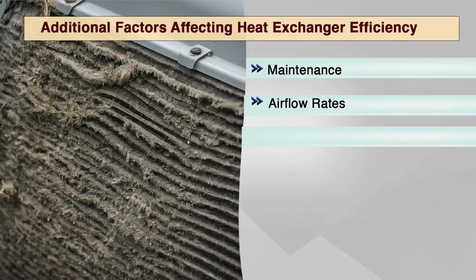Imagine these clogged heat exchangers. See how the dirt built up restricts airflow and reduces the surface area available for heat transfer. Regular cleaning helps prevent this scenario and maintain optimal efficiency. Second is airflow rates. For air to air heat exchangers, proper airflow rates are critical. If the airflow is too low, the heat exchangers will not have enough contact time with the air streams to transfer heat effectively. Conversely, excessively high airflow rates can also reduce efficiency. A well designed HVAC system will ensure optimal airflow for the specific heat exchangers being used.